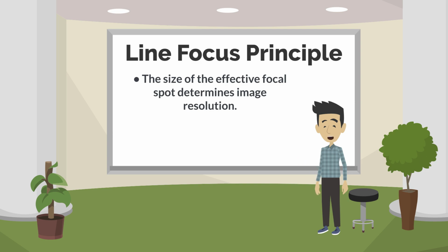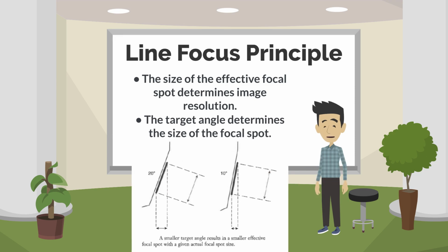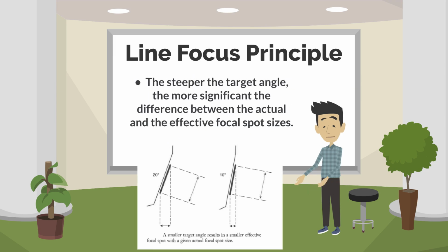The size of the effective focal spot determines image resolution. The target angle determines the relative size of the effective focal spot. The steeper the target angle, the more significant the difference between the actual and the effective focal spot sizes.